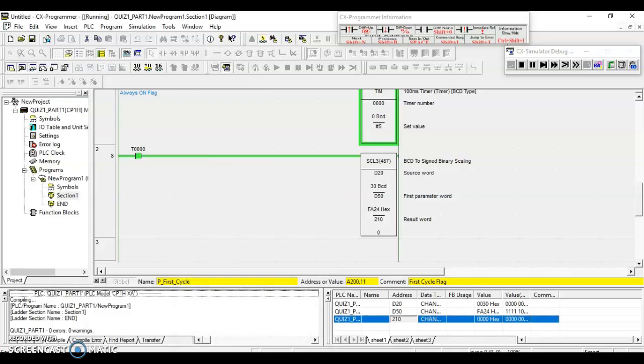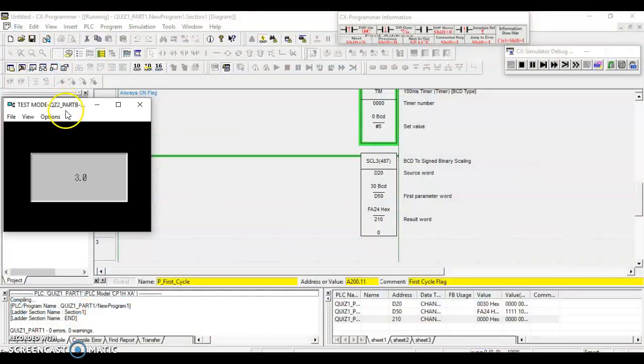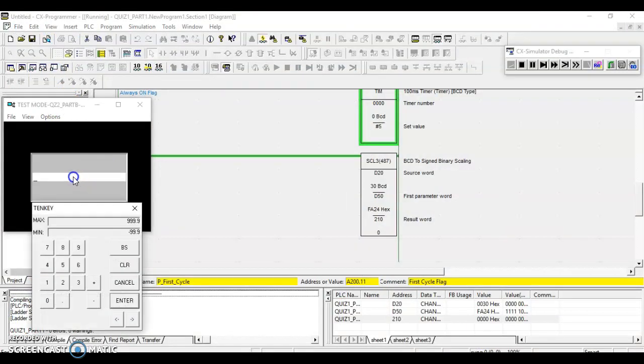So now we're going to test the maximum input, which is 15. And since 20 milliampere is the maximum output, we should expect a PLC output of 1770.